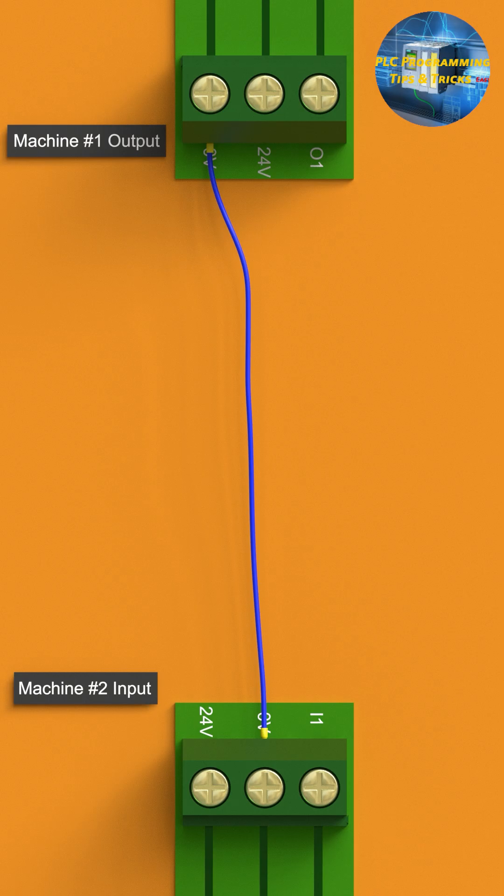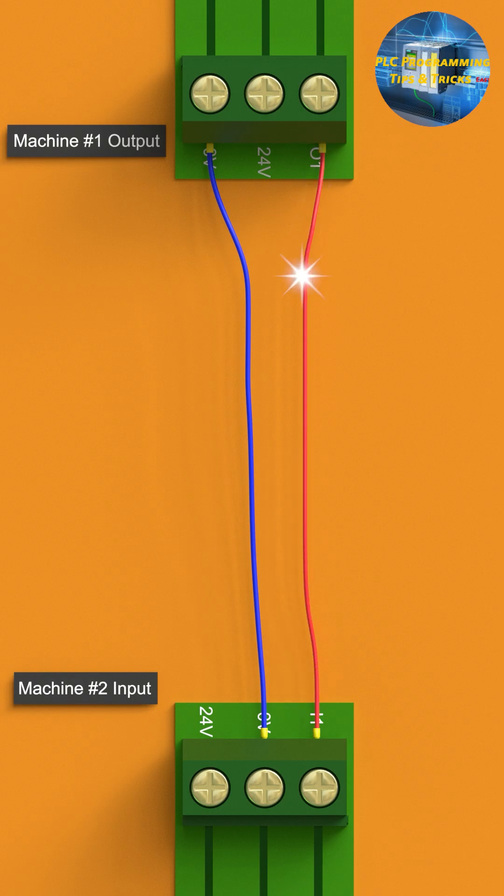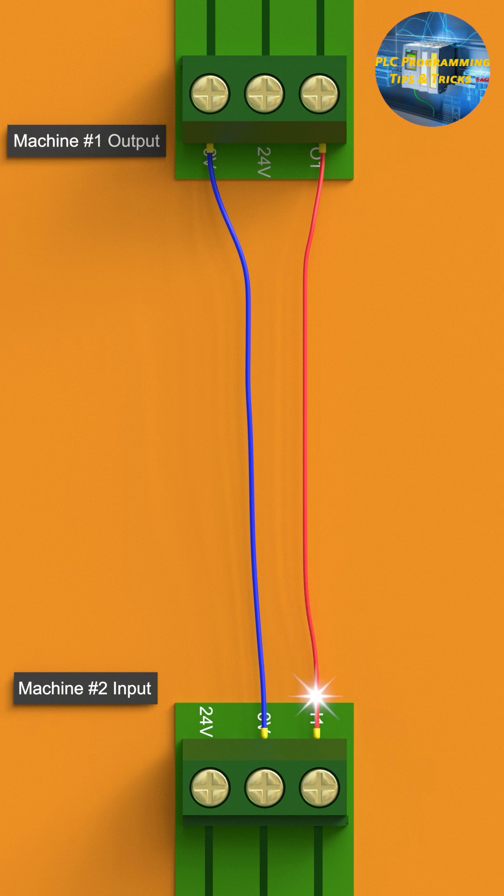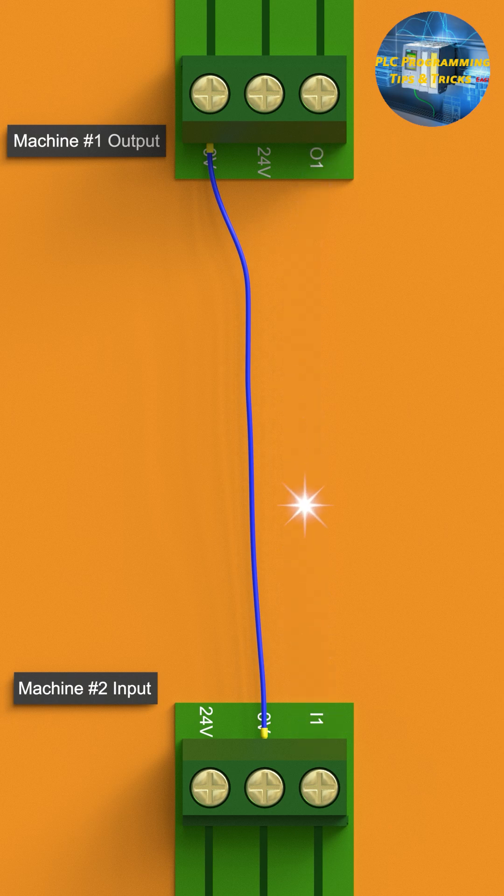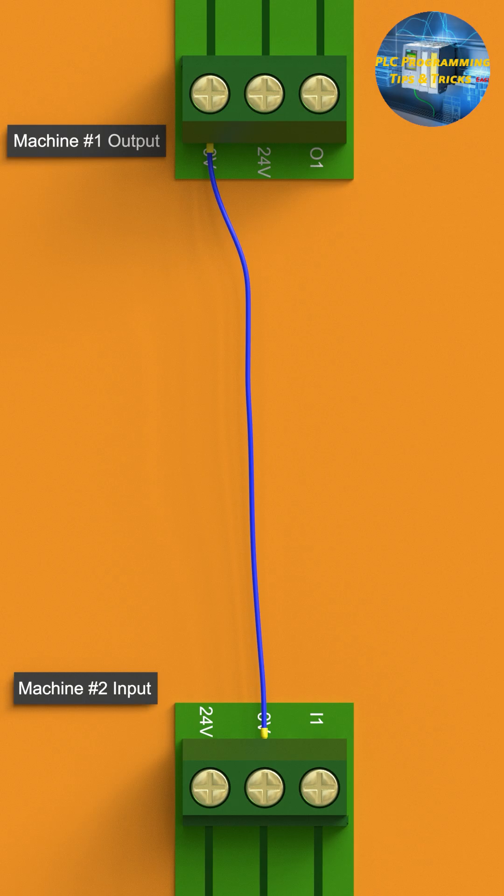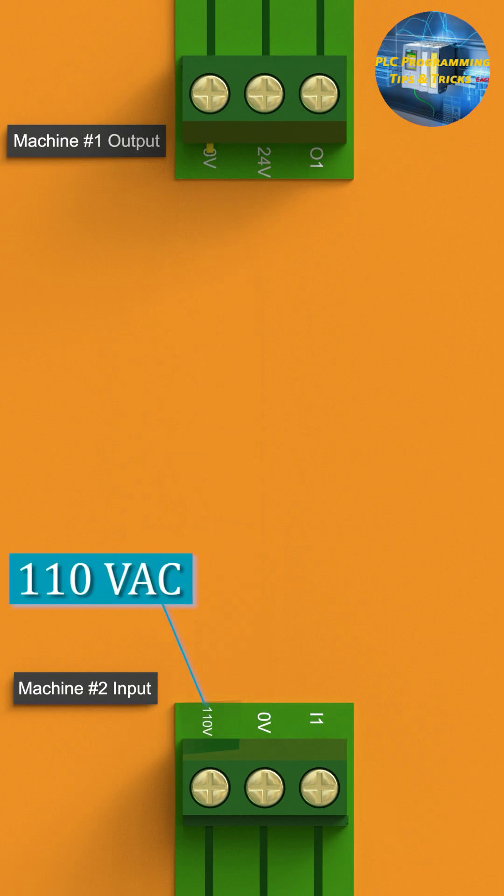Next we can simply connect the output of machine 1 to the input terminal of machine 2 with a wire. Now when the output signal from machine 1 turns on, the 24 volt DC reaches the input terminal of machine 2. This setup looks fine until now, but what if machine 2 requires 110 volt AC as an input signal?